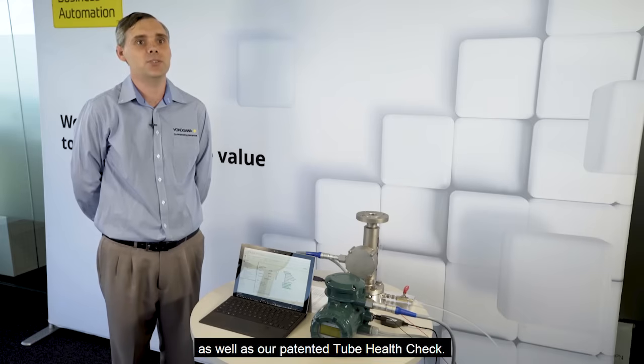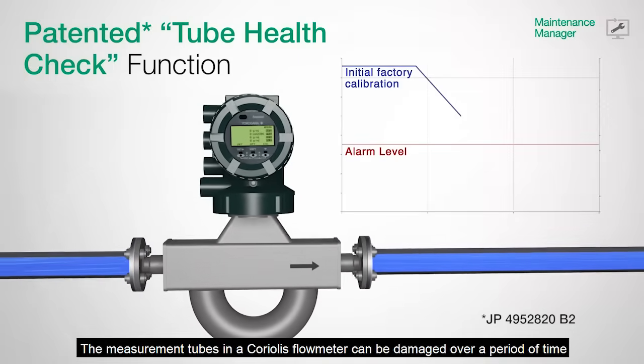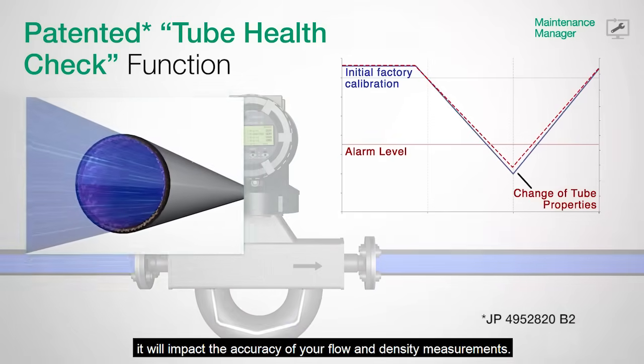The Rotamass Total Insight Coriolis Flow Meter features built-in verification as well as our patented tube health check. The measurement tubes in a Coriolis flow meter can be damaged over a period of time due to corrosion, erosion, or deposits. If the condition of the measuring tubes deteriorates, it will impact the accuracy of your flow and density measurements.